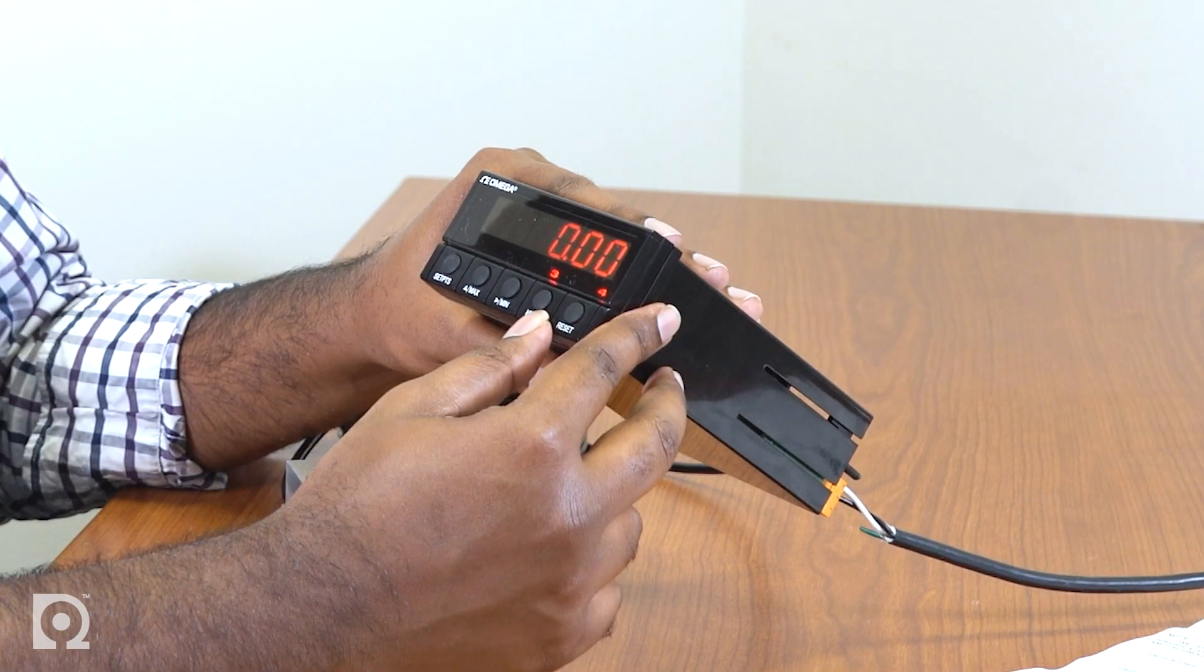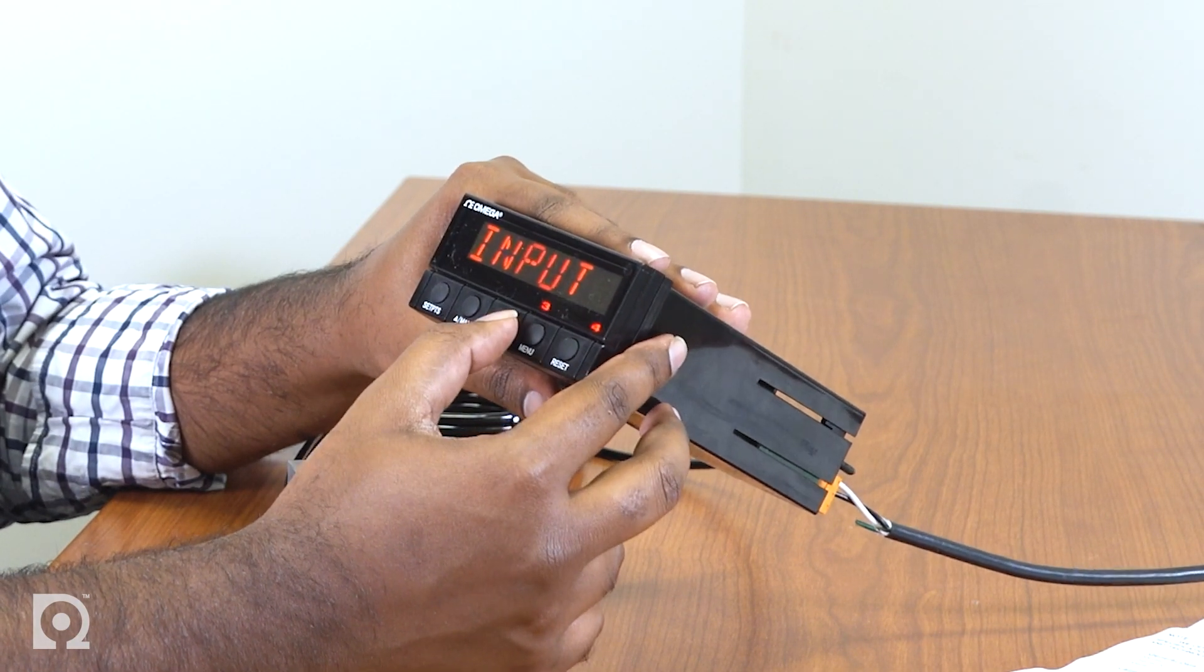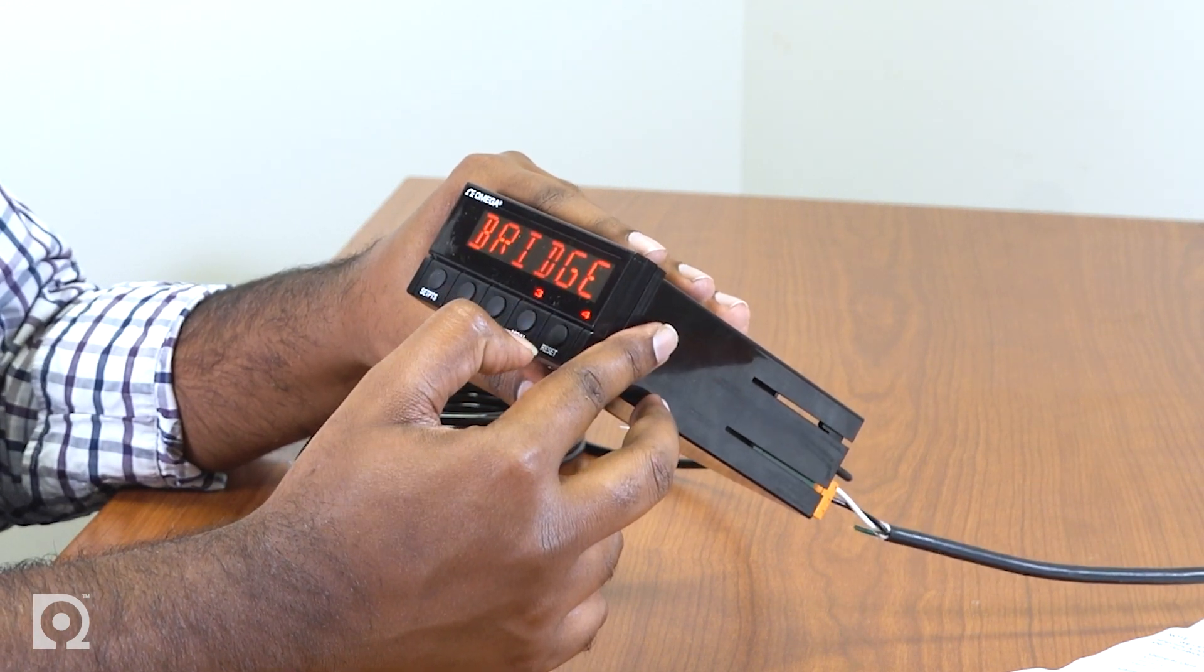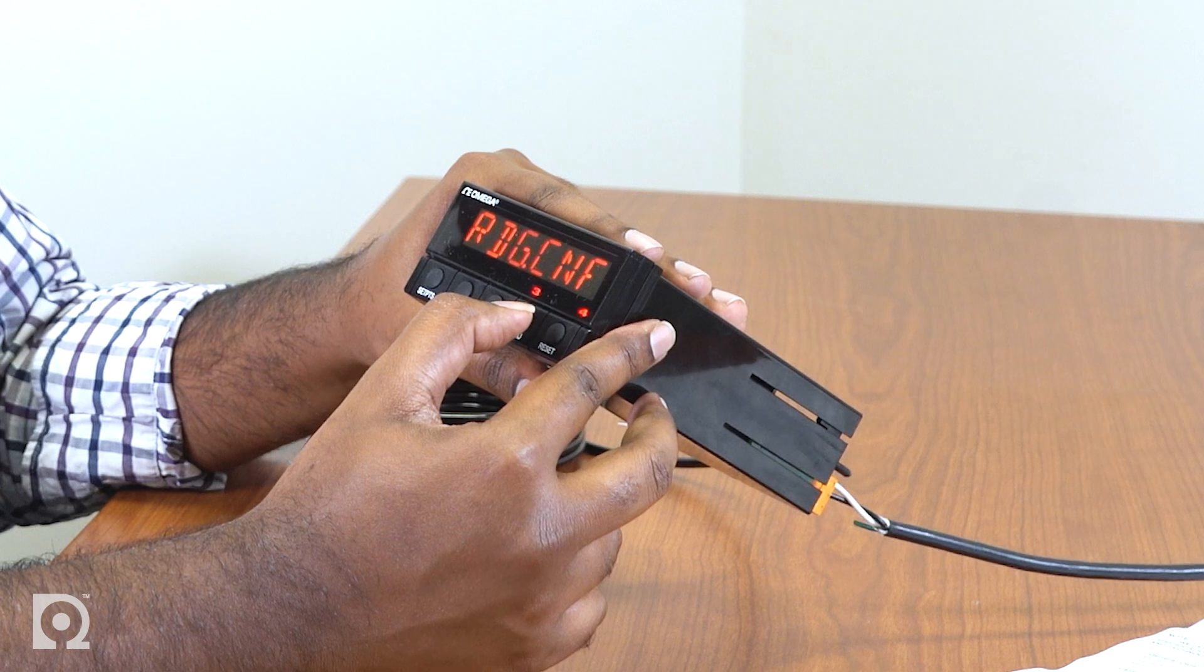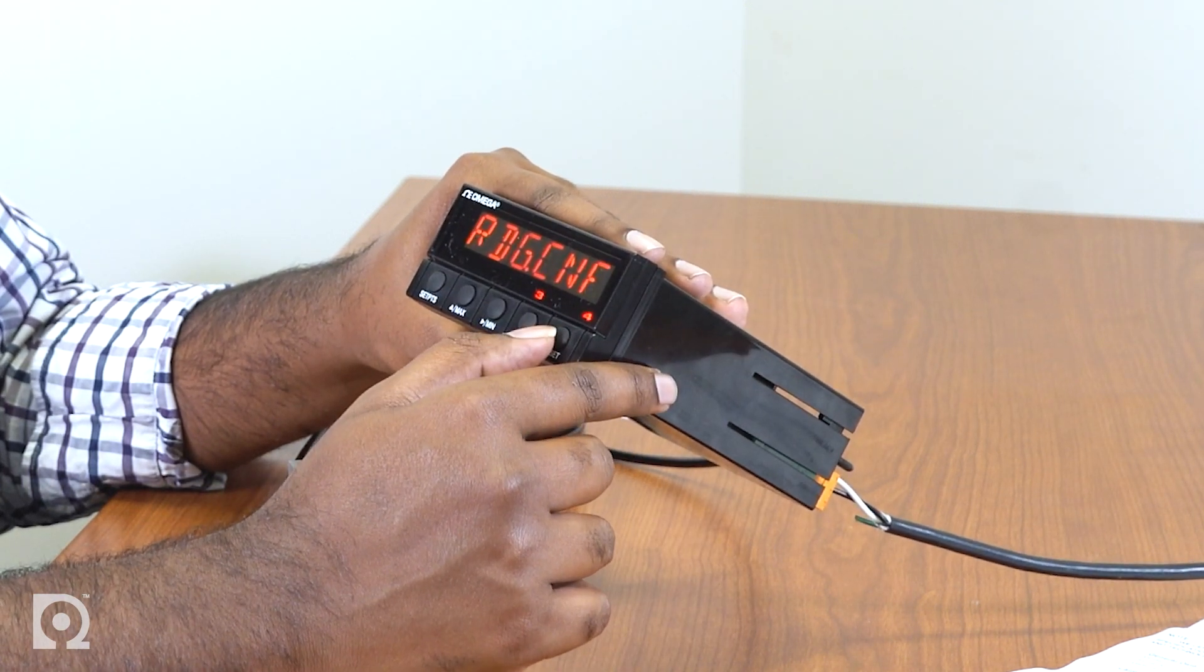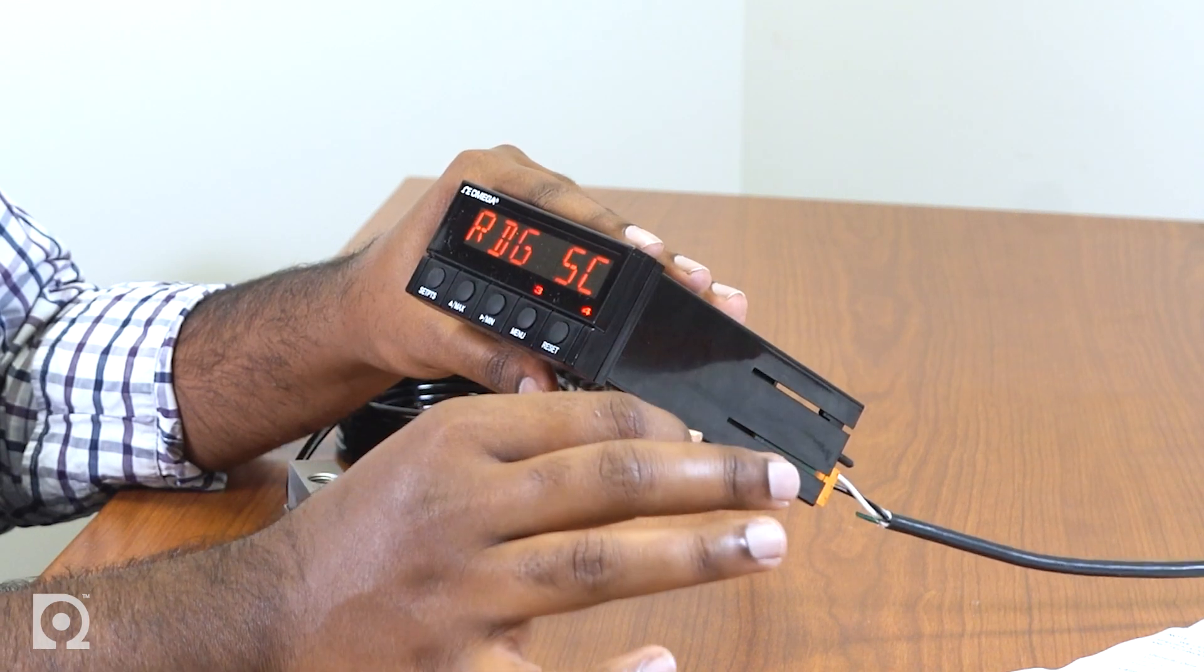So we have wired the load cell to the meter. Let's dive in and start pushing some buttons. To begin with, press the menu button until you see input. Now press the min button once, you'll see bridge flashing. Press the menu button once to save it. Press the menu button again, you'll see RDG.CNF. You don't need to make any changes in RDG-CNF. Press the menu button again, you'll see RDG-SC, which stands for reading scale.